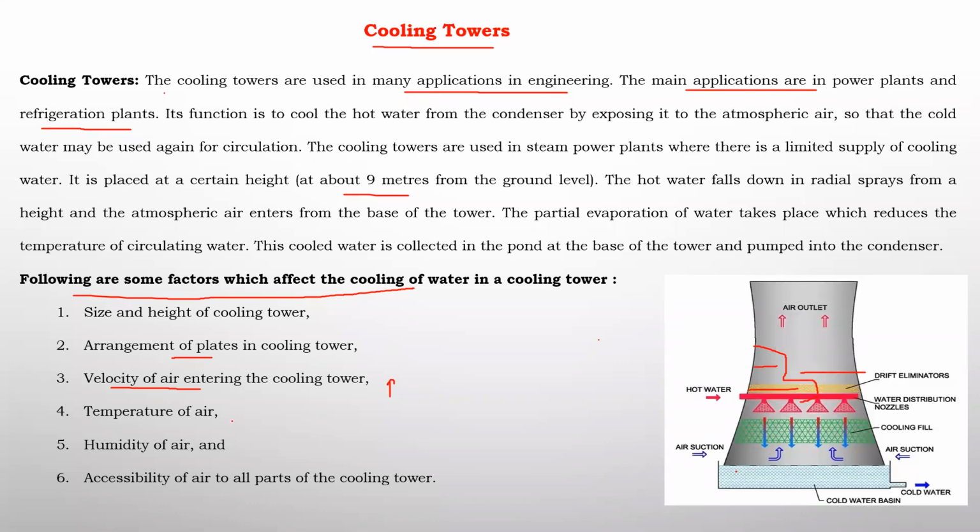And the temperature of the air: if the temperature of the air is high, the cooling rate falls. If the temperature of air is less, the cooling rate increases. Because with the temperature of the outside air only we are cooling the water inside this chamber, right? If the velocity increases, the cooling rate increases. If the velocity decreases, the cooling rate decreases.